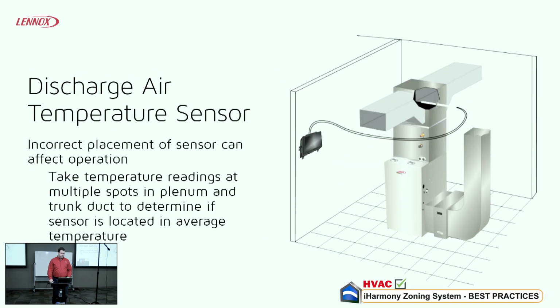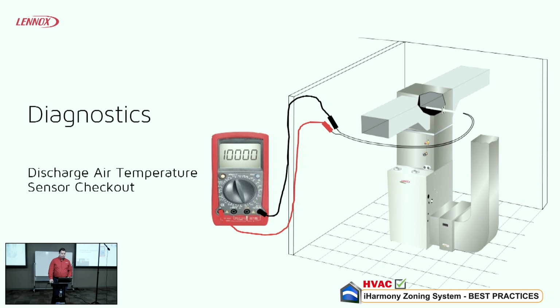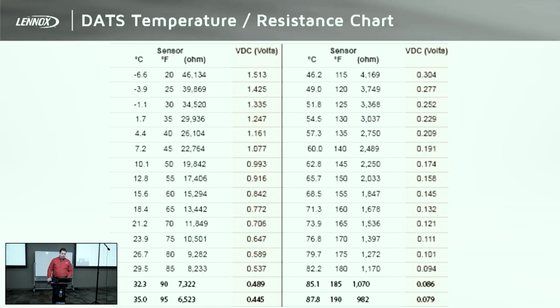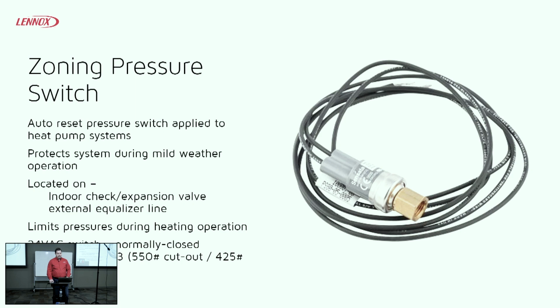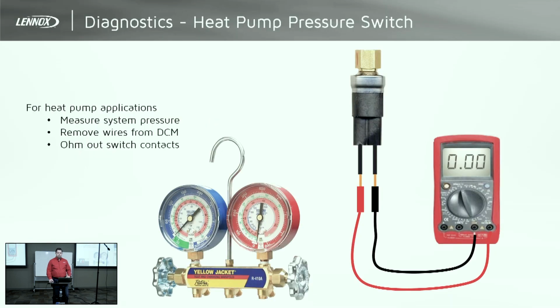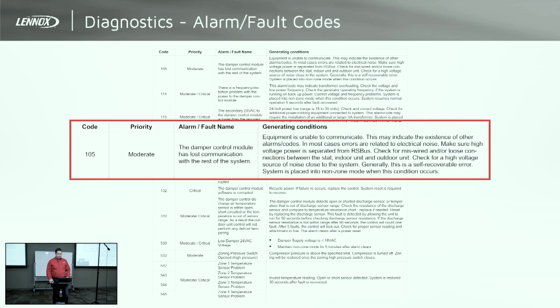We've been over the discharge air sensor, the zone stat and what we're going to see there. As far as diagnosis, it's a thermistor. You can just check ohms across it. There's a temp resistance chart in the installation manual that'll tell us what it's reading and if it's correct. We talked a lot about the zone pressure switch. It's just an on-off. You're going to ohm it out. It's either going to be closed or open. Again, something very basic.